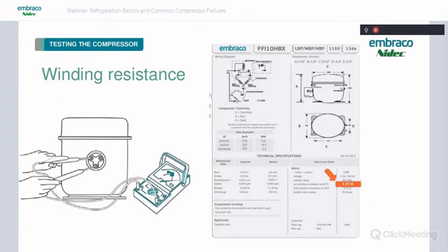So we're looking for shorted windings. We're looking for open windings. Any kind of short or anything is going to skew these readings. Of course, you can read from start to run if you'd like. Basically, all that's doing is you're reading through both windings, so you're going to have the sum of both resistances. There's really no need if you read from common to run, common to start. That's kind of going to tell you if the compressor motor is good or not.